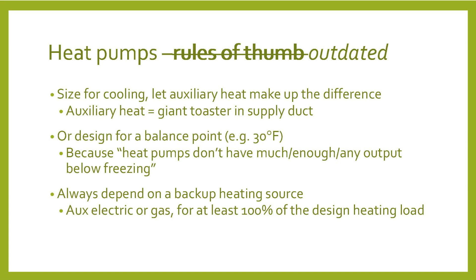So some of the rules of thumb for design, which I would say are outdated but still a lot of people think this way: size the unit for the cooling load in the building. You don't want to oversize for cooling because then you don't get good dehumidification. Are you actually designing for the humidity load? No, the ACCA manuals have a sort of a half-baked way of dealing with that, but it doesn't really deal with it, especially for low-load buildings.